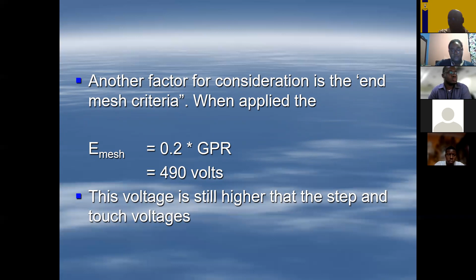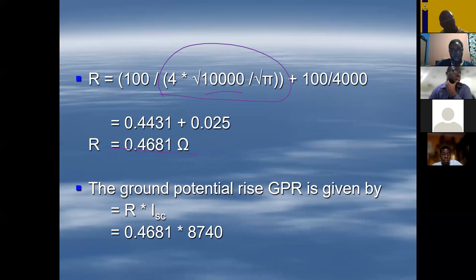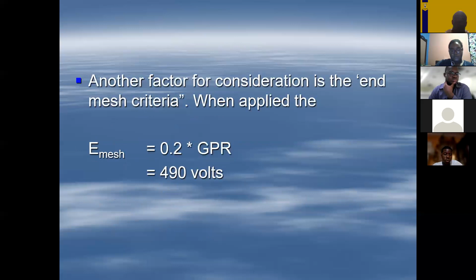So here is where I now need you to focus. We have gone through the process using the simplified formula - it's a little more detailed than that, but we'll put that in. We'll get all these values, the mat resistance, consider the maximum fault current possible, and then apply the factors. We see what our mesh value is, whether or not it is okay in terms of step and touch potential. If not, we look at other solutions, and one is to change the spacings.